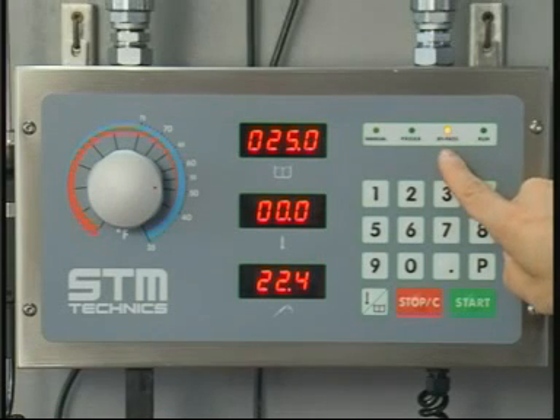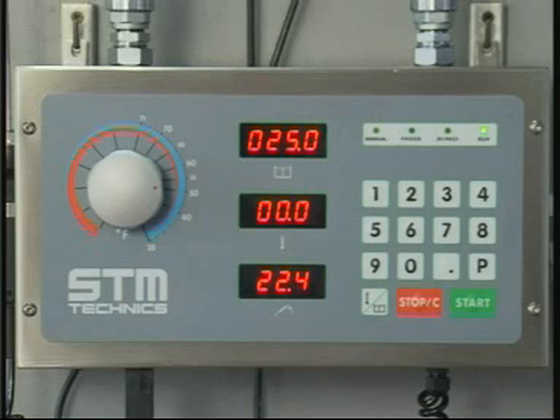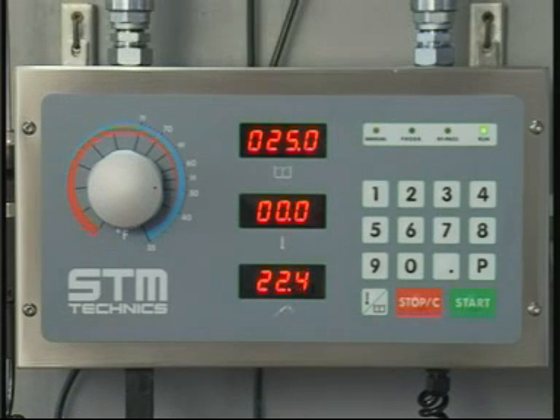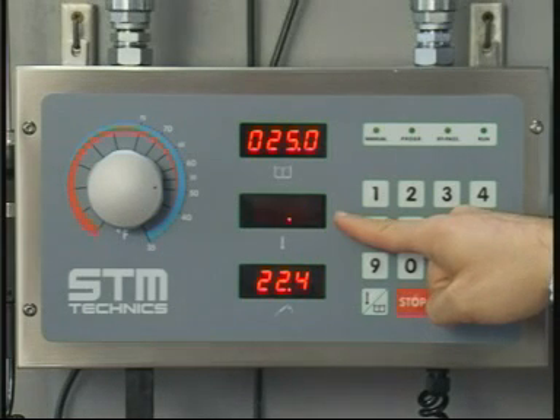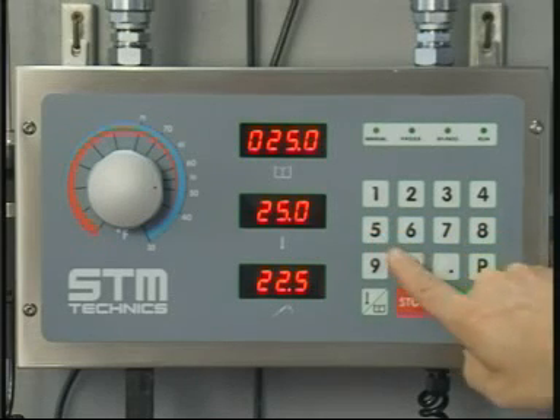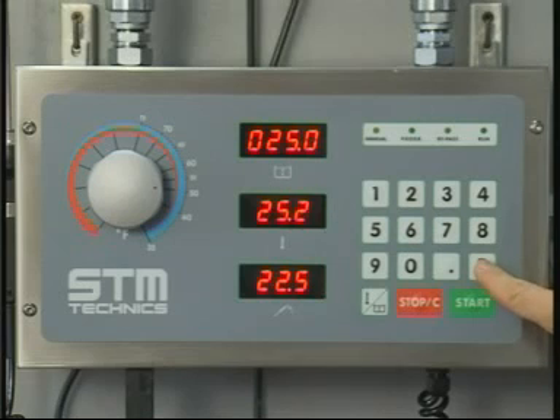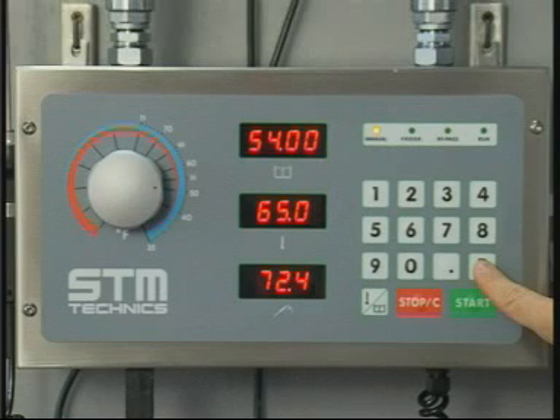Pressing start, the machine discharges the programmed litres, which are preset at 25, but the quantity can also be changed. Once the dosing is completed, the sign 00.0 flashes on the central display. Weigh with a scale the actual discharged quantity and input this value into the machine. The measure is always in litres, and the value cannot be shifted by more than 10% of the set quantity. For example, if the litres set were 25, it is possible to have a value from 22.5 to 27.5. Outside this range, the litre counter must be replaced. Press P to return to the normal state of the machine.